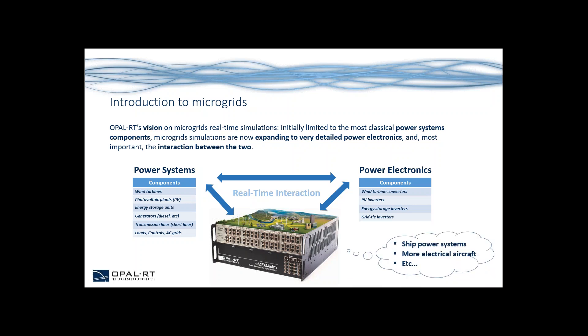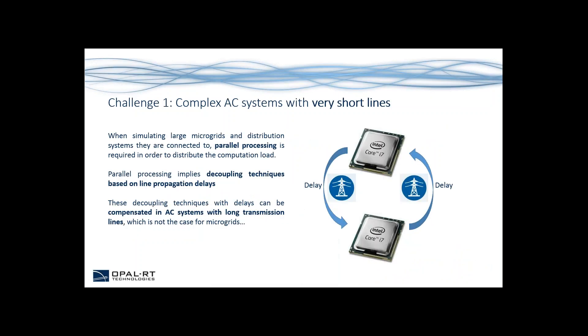One thing that is very important is how we can have a real-time interaction between those two groups of components. At Opal RT, we also consider that ship power systems and more electrical aircraft can be considered as microgrids, mainly because they bring the same type of challenges in terms of real-time simulation. The first challenge is that there are complex AC systems with very short lines that need to be simulated in real-time. When simulating large microgrids and distribution systems, parallel processing is required to distribute the computation load. However, parallel processing necessarily implies using decoupling techniques based on line propagation delays, and these delays cannot be compensated in microgrids since long transmission lines are typically not available.